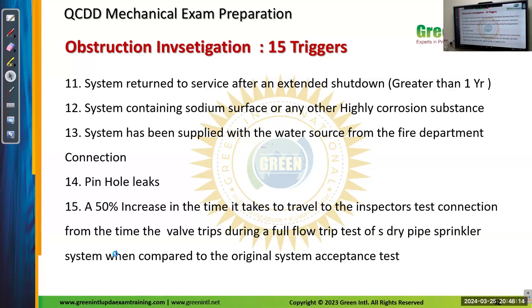So nitrogen or air. So in that, if you are taking a drain test, it means it's a hydro test. So if the water is available, that time consumed will be lesser. But if you are opening the dry pipe sprinkler systems, first the dry air will come, and only after that the water will come. So the time between the testing condition and original conditions will be different. I don't know how much percentage it is, but here it is mentioned as 50%. If even one item happens, it will not be approved.